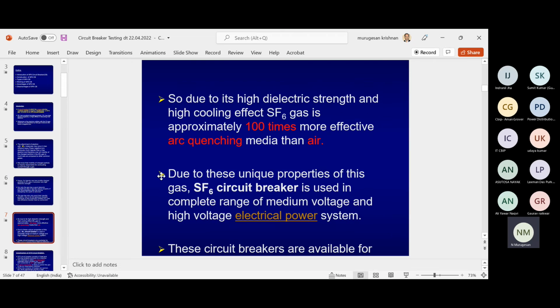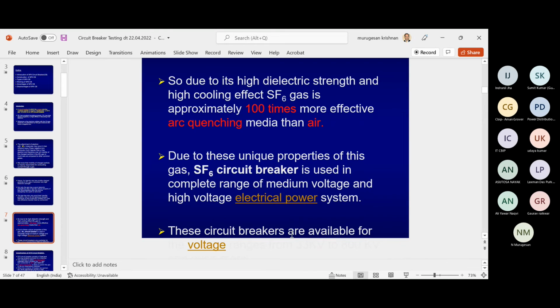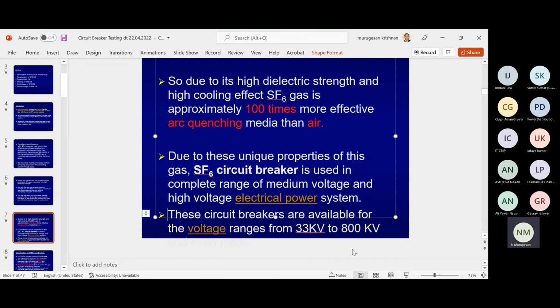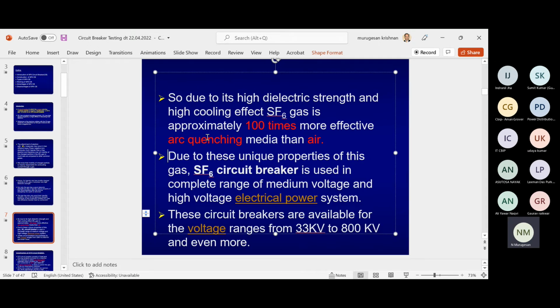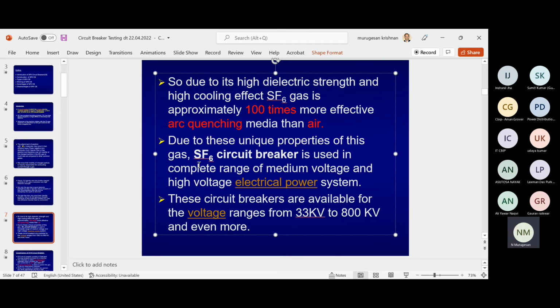I'll go a little faster. Due to the high dielectric strength and high cooling effect, SF6 is 100 times more effective than air. This is important. Due to this unique property, it is used across the complete range of medium voltage and high voltage circuit breakers. They are available, but handling SF6 is a very tricky and involved thing. You cannot handle it just like that because you cannot leave it in the open air.